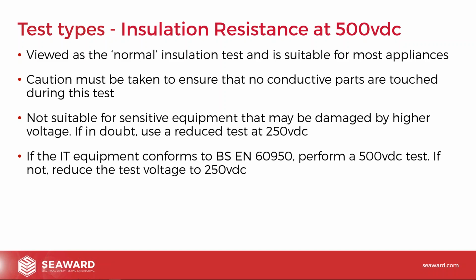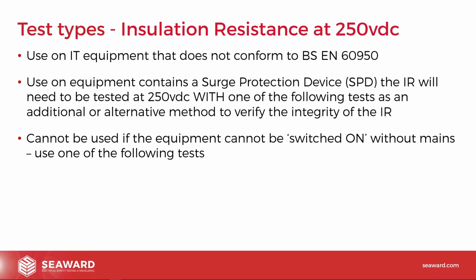So insulation resistance, 500 volts, our standard insulation resistance test. It's the one we use really on most equipment to check that there's no short circuits between the live parts and the protective conductor or any exposed parts. 250 volts, as we've said, we'd carry out this on IT equipment that doesn't conform to BS EN 60950. We'd also do it on any surge protected equipment or sensitive equipment to make sure that we were getting good readings on that and we weren't causing any damage.